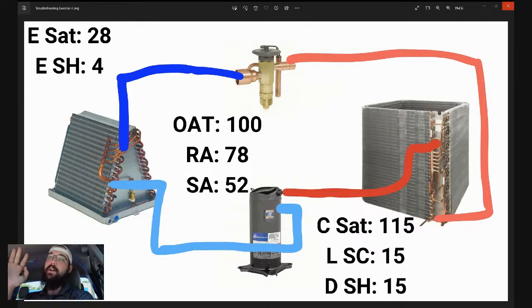Okay. So I chuckle, but in all actuality, let's talk about that. That is something that comes up frequently. We can rule out inefficient compressor for a couple of reasons. I know you may mean it as a joke, but taking it in a serious sense, the evaporator saturation, the fact that it's low, and the fact that our condenser saturation is adequate, it's 15 above ambient, so it's perfectly fine. And the fact those two are there would be a hard indicator that that compressor is pumping. We're moving refrigerant through the system.